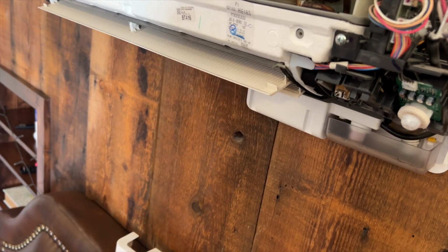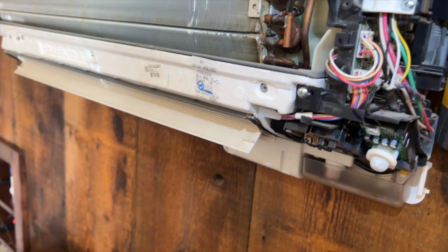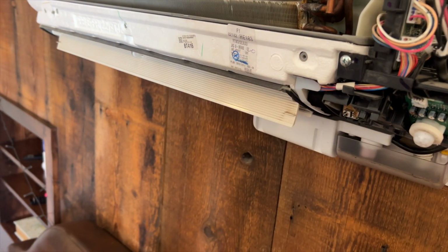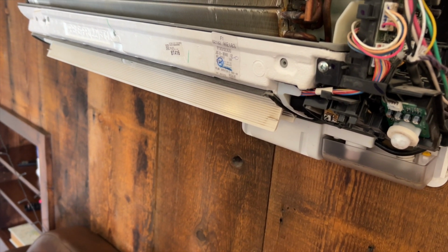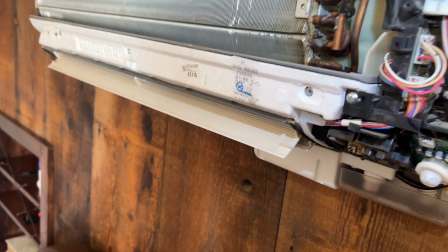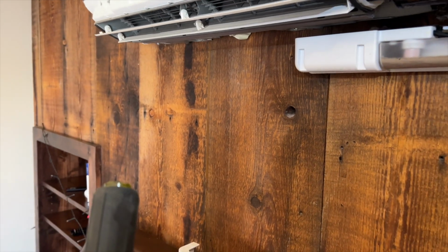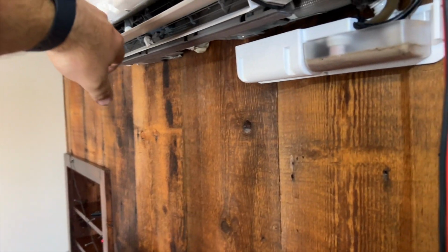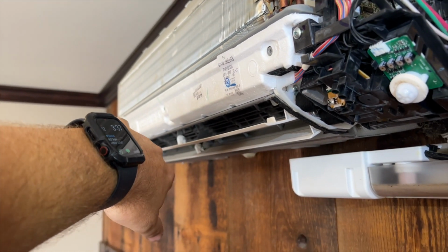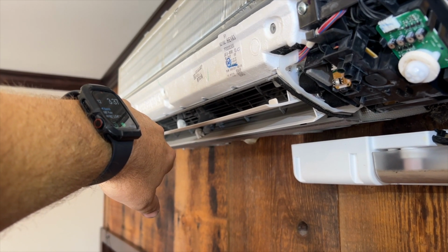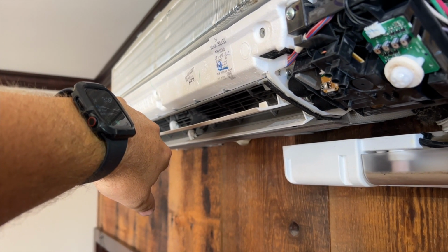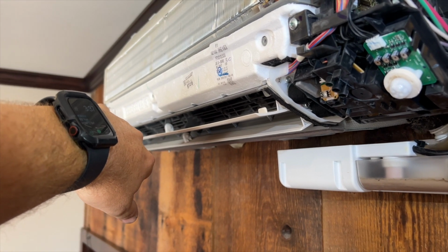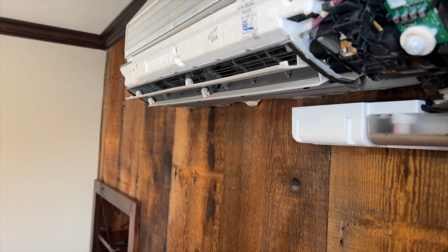Then the next thing we want to check is 4 and 1. And that's going to be our rotation pulse input. Looks to me like the fan's working fine. We got air coming out. Oh. Yeah, so it would appear that the motor is going bad.